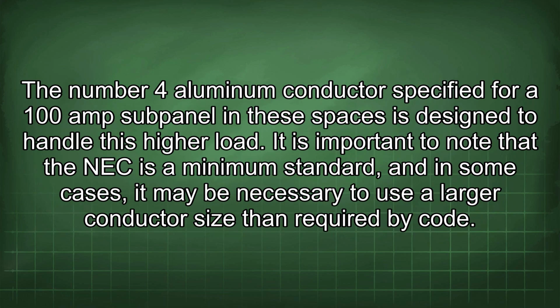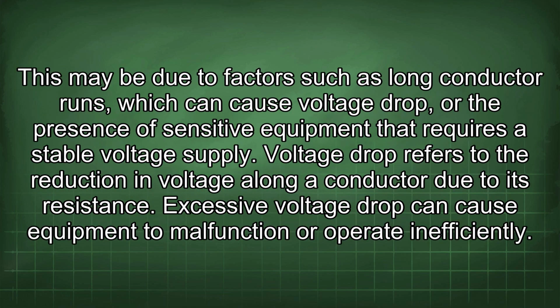The number 4 aluminum conductor specified for a 100 amp subpanel in these spaces is designed to handle this higher load. It is important to note that the NEC is a minimum standard, and in some cases, it may be necessary to use a larger conductor size than required by code. This may be due to factors such as long conductor runs, which can cause voltage drop, or the presence of sensitive equipment that requires a stable voltage supply.